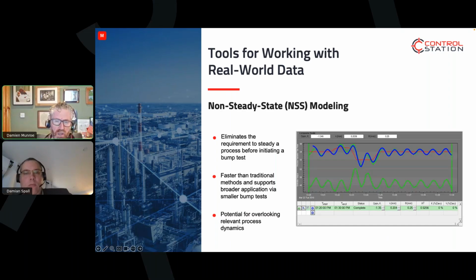Next slide, please, Vera. We have tools that support this. What you're looking at there is our modeling with non-steady state. If you were to try and calculate the gain, time constant and dead time on that from our classic model calculation, it would be somewhat problematic in finding exactly how much output change there was for the PV response. So in automatic, you need tools to support that.